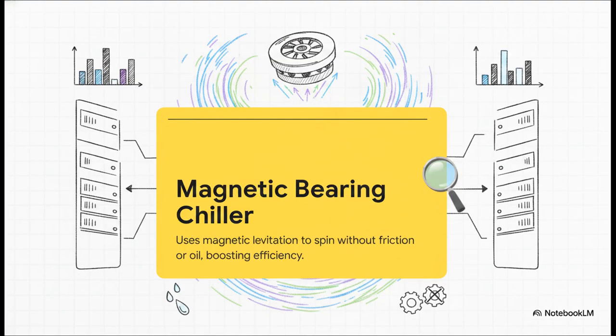Engineers have taken the compressor and given it a sci-fi upgrade with the magnetic bearing or oil-free chiller. They've started literally floating the compressor axis using magnetic levitation. This completely eliminates physical friction and the need for lubricating oil. Why does that matter? Well, it delivers shockingly high efficiency, especially when the data center isn't running at full load, which is most of the time, since workloads are constantly fluctuating.